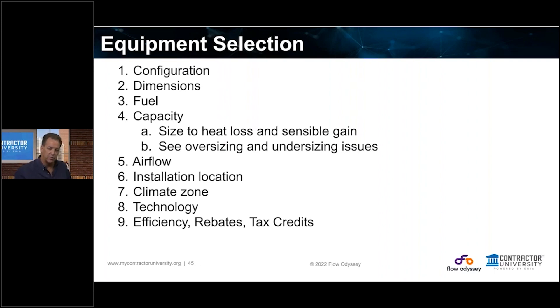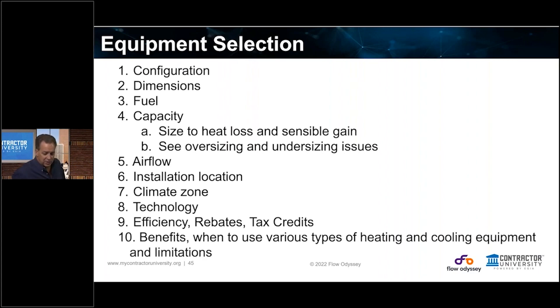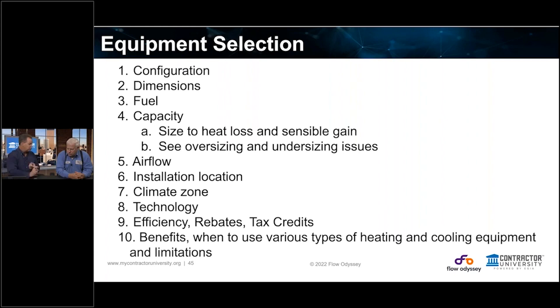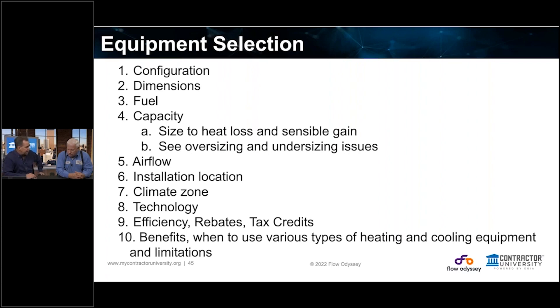What are the benefits of the various types of equipment? There's two-stage equipment on both the heating and cooling side, as well as heat pumps. There are variable speed fans and X13 constant torque fans, and modulating furnaces. The super new high-efficiency technology does a better job getting a cold coil, but some of it just doesn't dehumidify well enough. That's one reason I like two-stage equipment better than some of the variable speed equipment — a cold coil is what takes the moisture out.